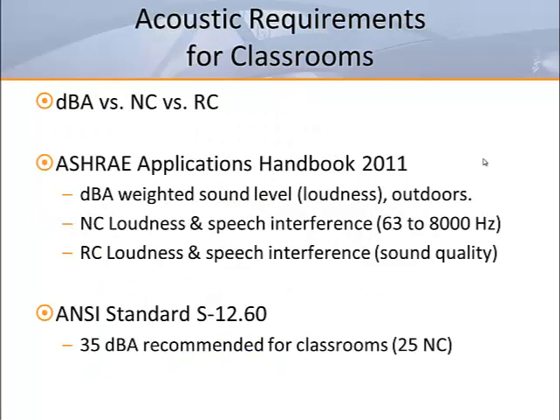There are many methods used to evaluate and specify sound requirements. ASHRAE Applications Handbook says that dBA is a weighted average that can be used to determine loudness, most typically used for outdoor noise requirements. NC is typically used to quantify sound for HVAC components to identify loudness and speech interference in the 63 to 8,000 Hz frequency range.